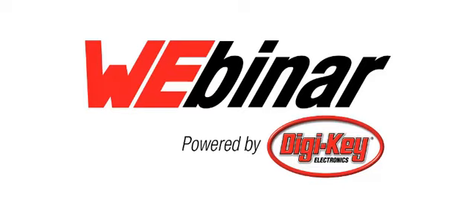Yes, it's possible to optimize the PCB tracks in the application, but the PCB tracks do not have as big an influence on the whole system as the dissipation through the cable. That's why we told you about the dissipation in the cable first, and we did the tests with the PCB at the moment. But I can give you very good information, I think in July or August, when we are ready in our labs with our tests, and then I can tell you how to optimize the tracks too, and you will find this also in the design guide for our terminal blocks, then online. Let's say in August it has to be online on our web page.